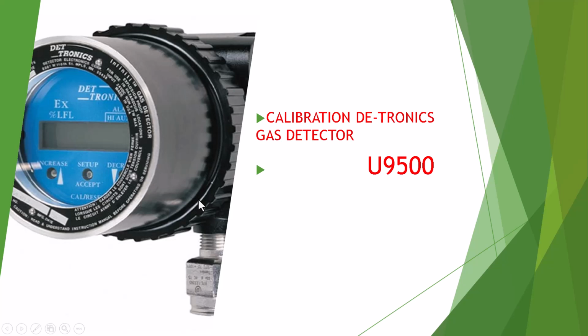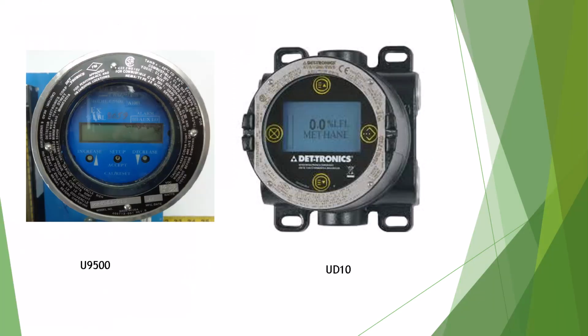Hello, today I talk about how to calibrate the Det-Tronics gas detector U9500. The U9500 is an old gas detector, but it's still used on site. It's completely different from the new Det-Tronics gas detector UD10. Here's the UD10, the new one. Easy calibration: put the magnet here. We choose the menu in this display, but the U9500 has just a small display, so it's sometimes confusing.